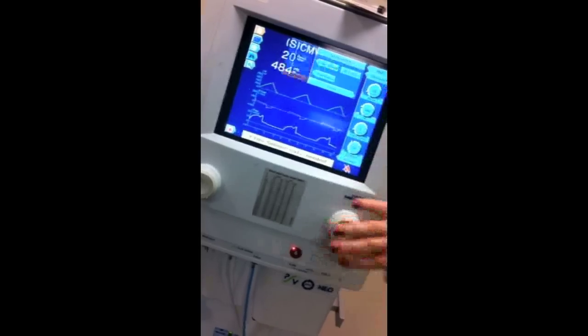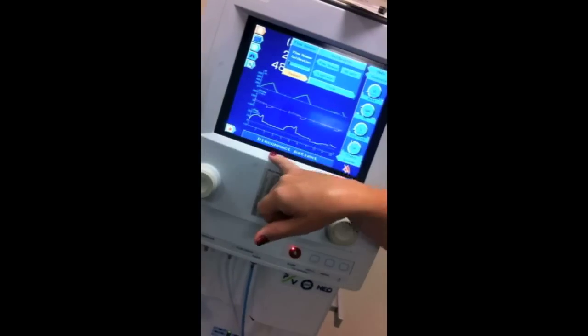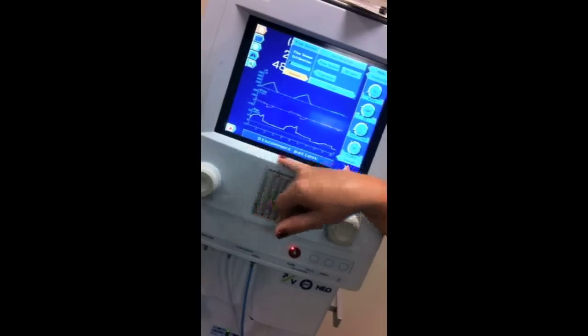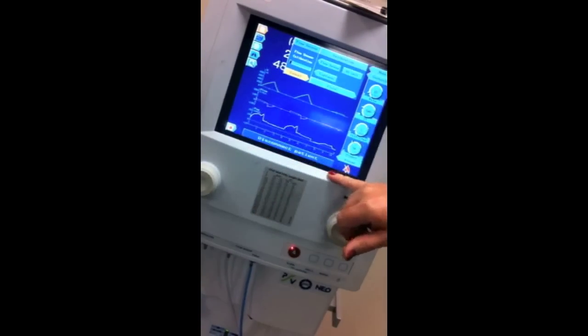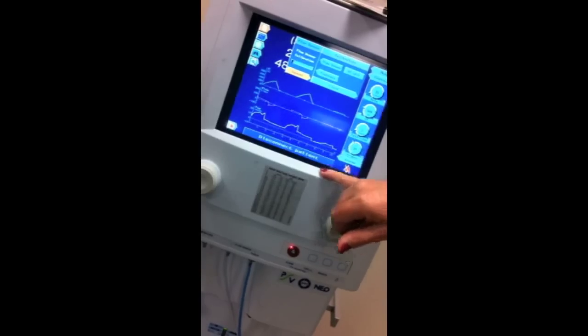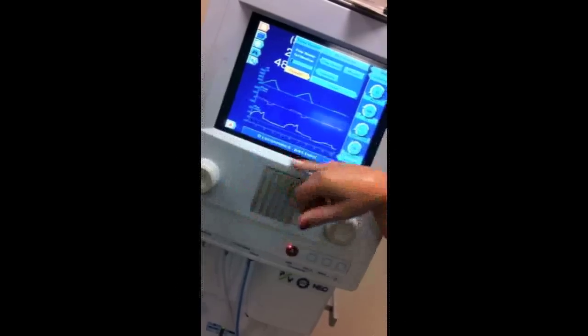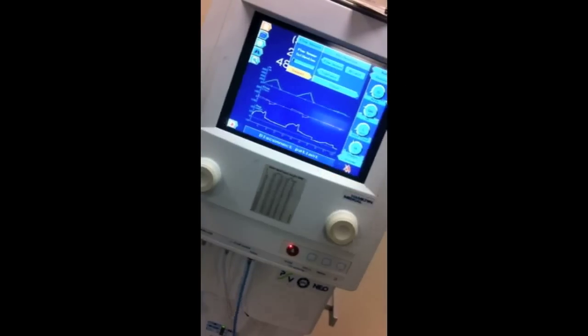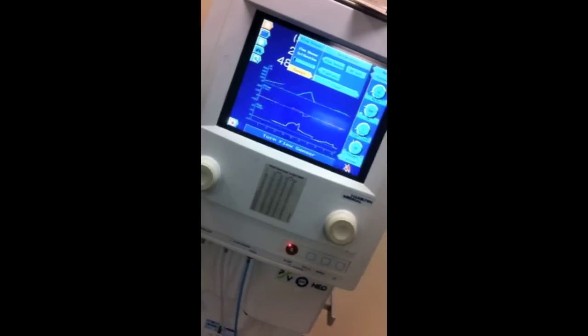So again, we're orange, we hit it. All the calibration comes in blue at the bottom, so you need to pay attention to the blue wording that comes up. It tells you exactly what to do, just like the other ventilators, but sometimes you're going to have other colors coming up. You need the blue. So it's telling us to disconnect our patient, so that's what I'm going to do. It will automatically sense it. Now it wants me to turn the flow sensor.